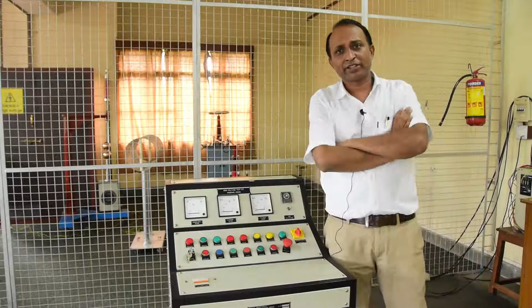So basically corona is ionization of air surrounding the transmission line conductors. Mostly the transmission of electrical power takes place at very high voltages, 220 kV or 400 kV. Due to such high voltages, the intensity of the electric field on or near the surface of the line conductor is very high, right? So the air surrounding the conductor has a tendency to get ionized.